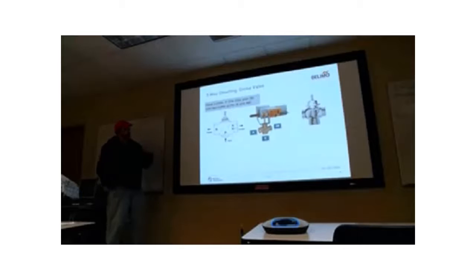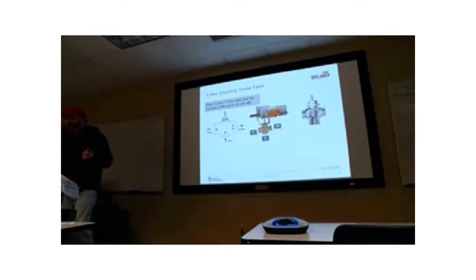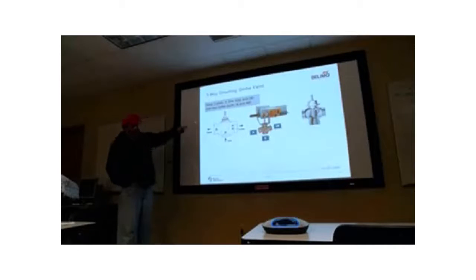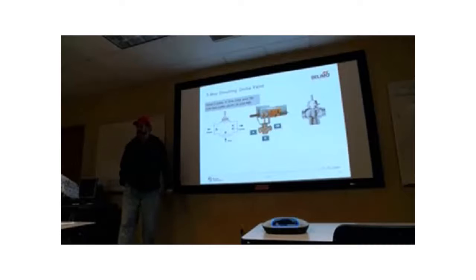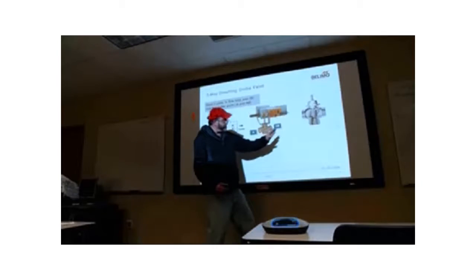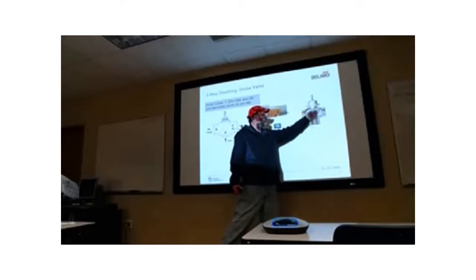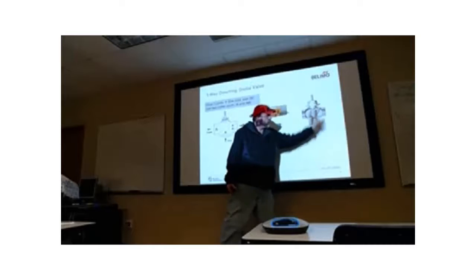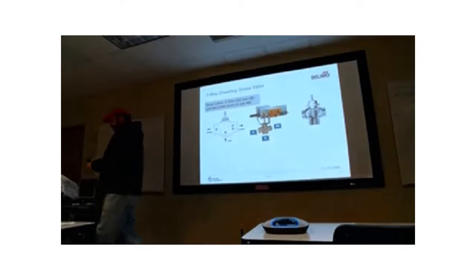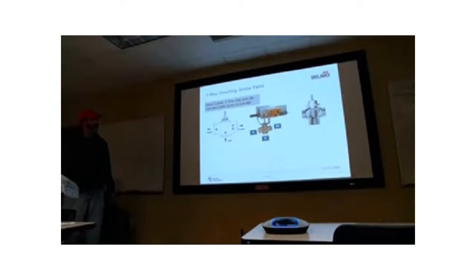Now, a diverting globe valve, remember I said with globe valves, you can't use a diverting valve for a mixing valve and vice versa. One of the reasons is, if you look over there on the far right, look at the plug. The plug's completely different, right? Remember the mixing plug was like this? The diverting plug is sort of like a barrel. And actually that plug is hollow. So the water can come up through this port and go through the plug and go out this side. And then the other part, when the plug lifts up, the water can go that way. That's why you can't use a diverting valve for a mixing valve and vice versa.